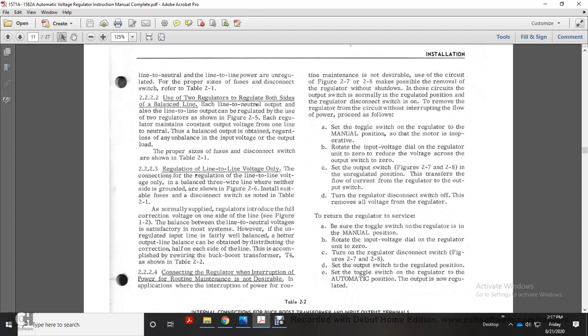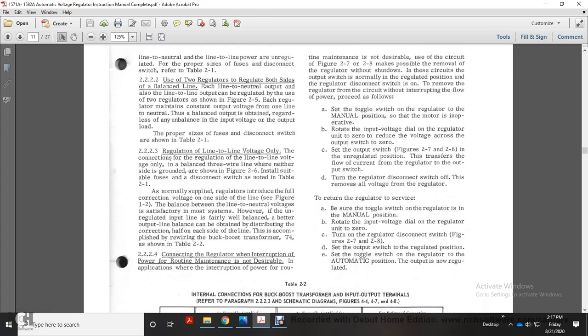2.2.3, regulation of line-to-line voltage only. The connection for regulation of a line-to-line voltage only on balanced 3-wire lines with neither side grounded is shown in Figure 2.6. Install suitable fuse disconnect switches noted in Table 2.1. Normally the supplied regulator introduces full correction voltage on one side of the line. Balance between the line and the neutral voltage is satisfactory in most systems. However, if the unregulated input line is fairly well balanced, Better output balance can be obtained by distributing the correction, half on each side of the line, and is accomplished with a rewiring of the buck booster transformer T4 as shown in Table 2.2.